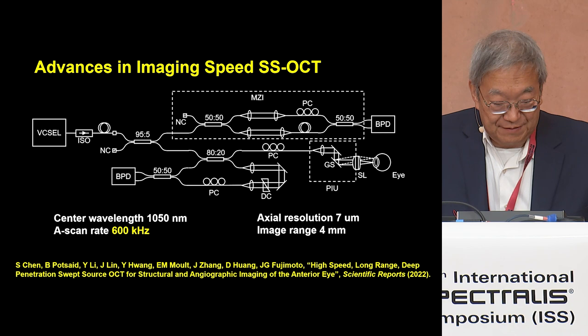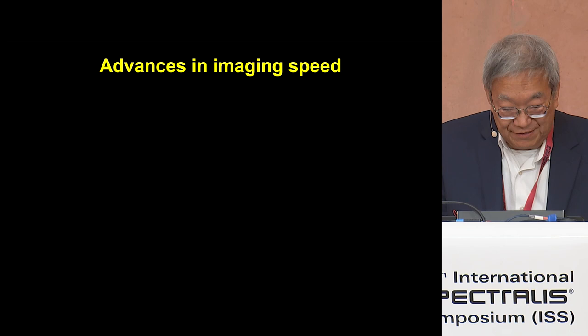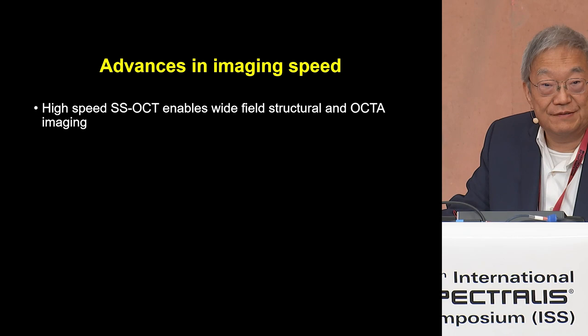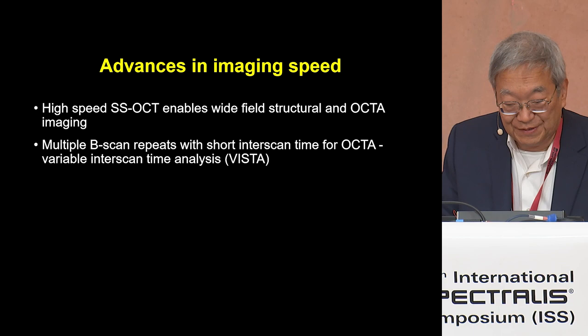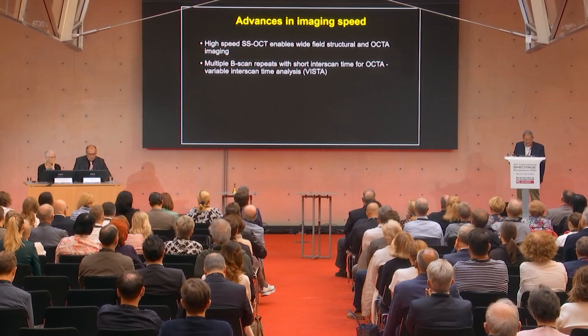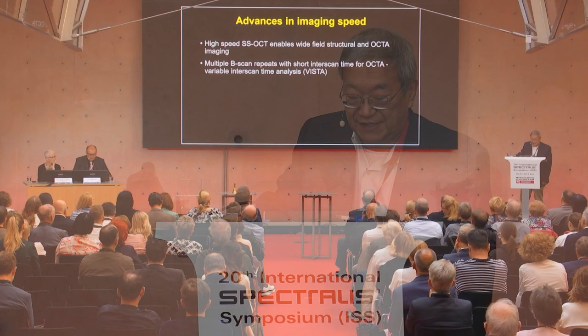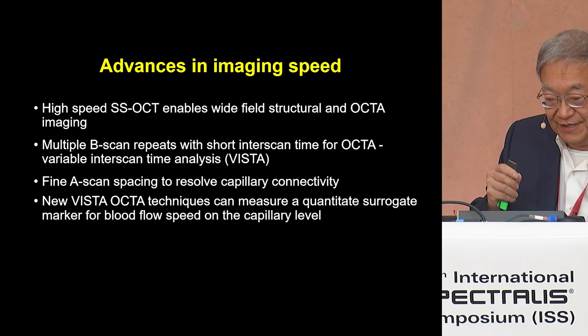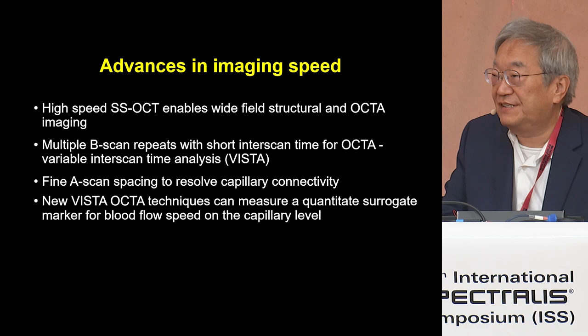The system is a prototype with a 600 kilohertz scan rate and 7 micron axial resolution. With high speed, we can do wide-field structural OCT and angiographic imaging. For OCT angiography, we can do multiple B-scans with very short inter-scan time. This allows variable inter-scan time analysis with fine A-scan spacing necessary to resolve connectivity on the capillary level. We can then do next-generation variable inter-scan time analysis, which can extract a quantitative marker for blood flow speeds on the capillary level.